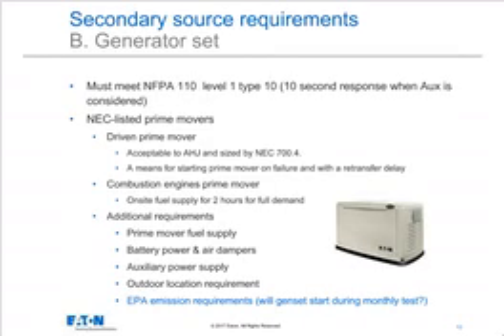The next one is a generator set. Remember, a generator set can function for emergency lighting by itself if it's the type of generator that starts and stabilizes within 10 seconds. And that's not uncommon for a small generator like you see in the picture here. Keep in mind that if I have a large building and a big old diesel generator sitting out back, I am going to be concerned that I don't necessarily want to fire up that giant generator every time there's a tiny blink in utility power.